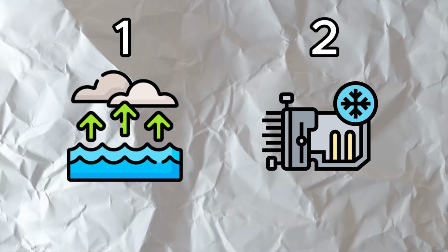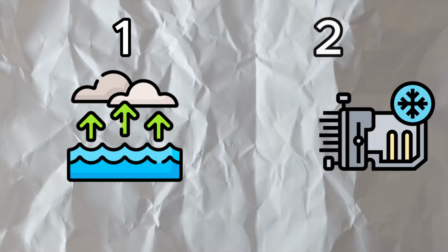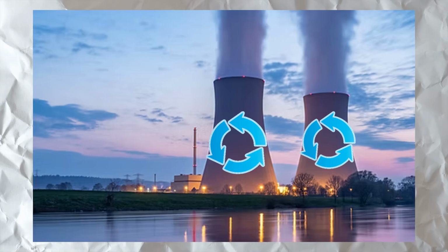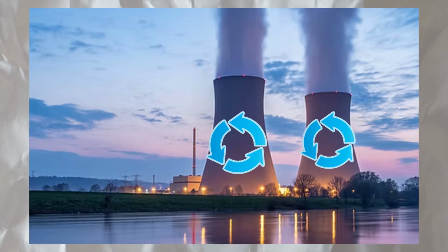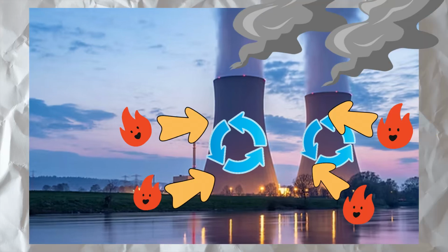There are two main cooling methods that data centers use, and the first one is evaporative cooling. Water is circulated through cooling towers and exposed to air, which causes some of it to evaporate, and this absorbs heat, thus cooling the system.